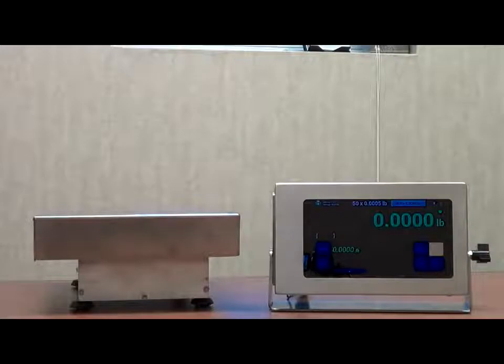This particular scale is a surface acoustic wave scale, or in short, SAW scale. This technology can show one part in 100,000. This is a 50 pound scale, but it can show up to four decimals due to its resolution.